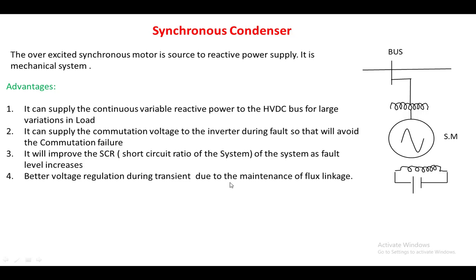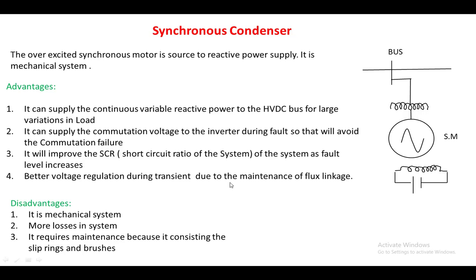The synchronous condenser gives better voltage regulation during transients due to the magnetic flux linkages existing in the synchronous motor. The disadvantages are that it is a mechanical system with higher losses, lower efficiency, and it requires maintenance because it consists of slip rings and brushes.